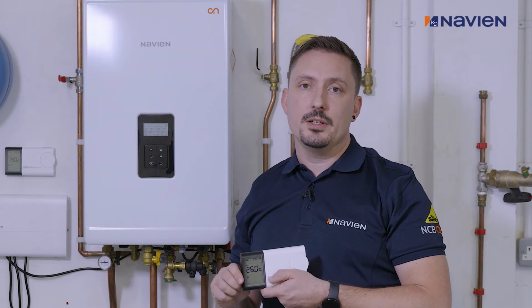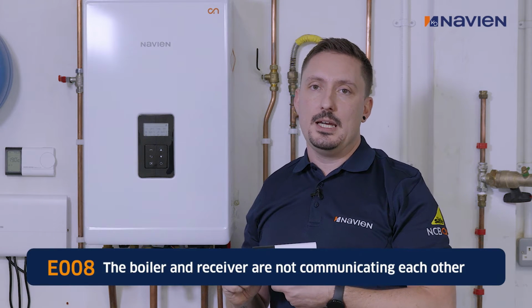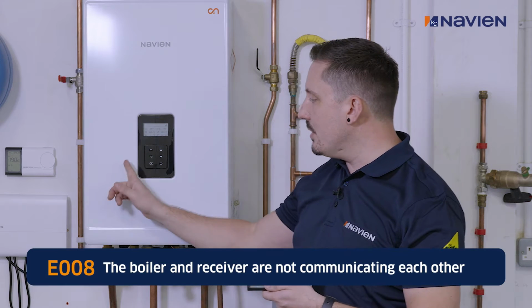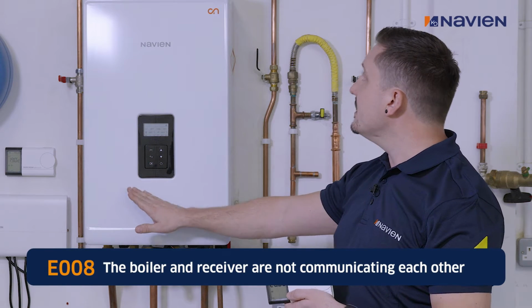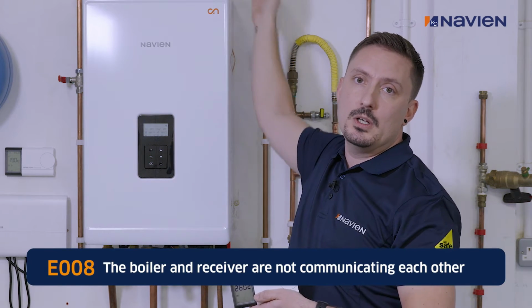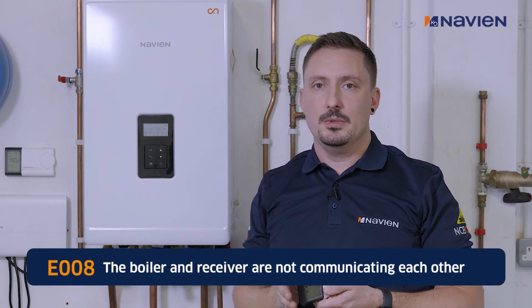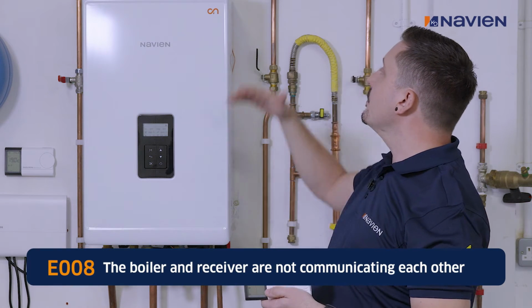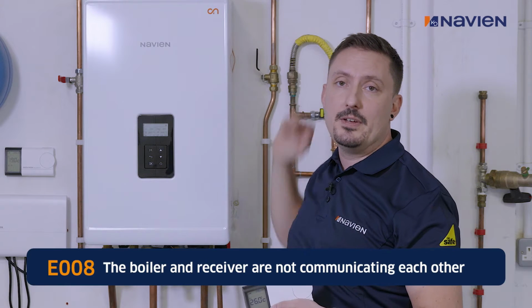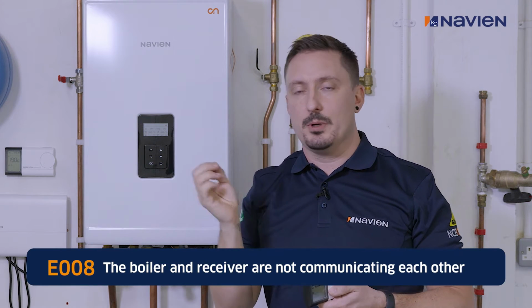And then the last one is E008. E008 is where the orange communication cable between the boiler itself and the receiver on the wall may have a loose connection. So the most obvious thing to do would be to check the block in the back of here. And it's quite simple, it's probably just a loose connection.